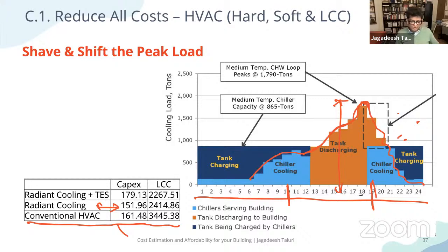Looking at the cooling profile, which you usually get from your energy simulation model, say I need a 2000 ton chiller, but I want to reduce my capex and optimize the whole scenario. So I may decide not to operate the chiller during the day, say between 12 and 6 o'clock, when the peak load or power demand is so high that the government isn't able to supply it during summertime. Power supply isn't there, so people rely on generators, which cost say three times more than conventional power. You're not able to do anything about that.